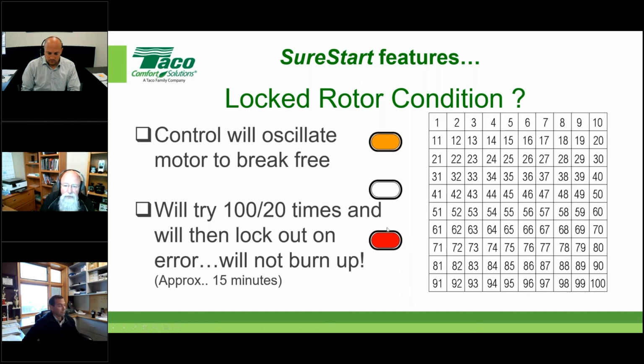The good thing about it is that when the service tech gets there and sees this red light, it doesn't mean the pump's bad. He's just going to disconnect power to the pump and take the pump apart, starting with the power head. Pull that apart and find out what it is full of: black iron oxide, or maybe a wood chip or a rock or something like that.